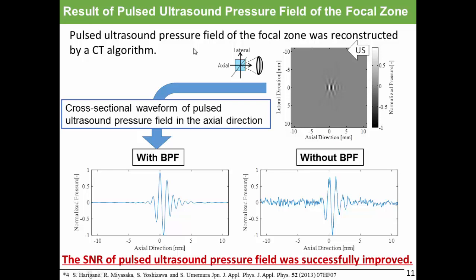Let me show the results of the pulsed ultrasound pressure field reconstructed by CT algorithm. This figure shows the reconstructed pulsed ultrasound pressure field of the focal zone. And these figures show the cross-sectional waveforms of the pulsed ultrasound pressure field without band-pass filter and with band-pass filter in the axial direction. In comparison with the waveforms without band-pass filter, the SNR of the pulsed ultrasound pressure field in this study was successfully improved.